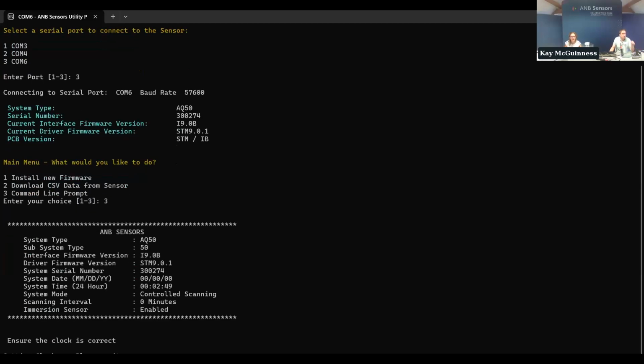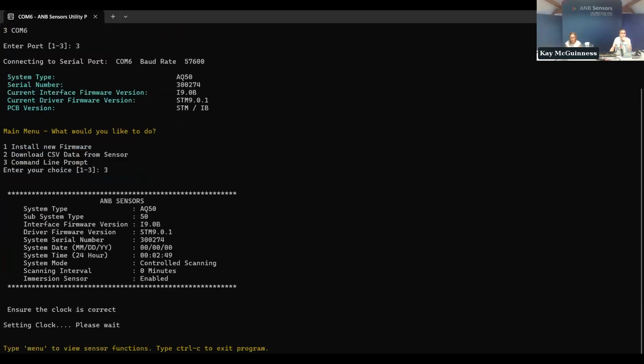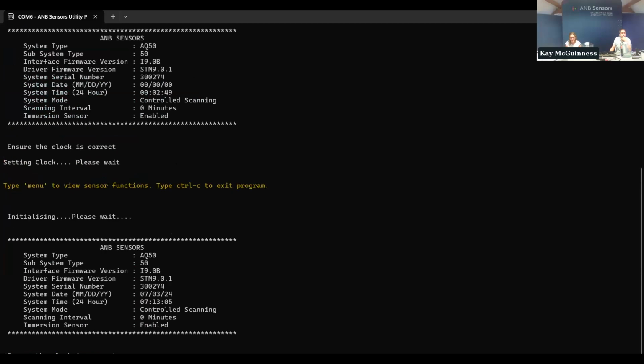And the splash screen of the sensor comes up. You'll note that there's no date or time. Utils, if it sees no date or time, automatically sets the date and time to that of the laptop or computer you're using. If you wait a few seconds, you'll get a new splash screen with the proper date and time, along with all the information about the sensor and the firmware versions.